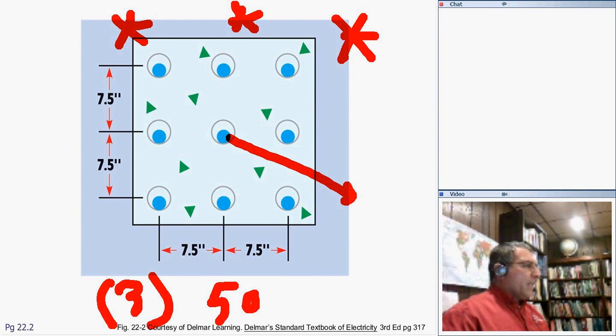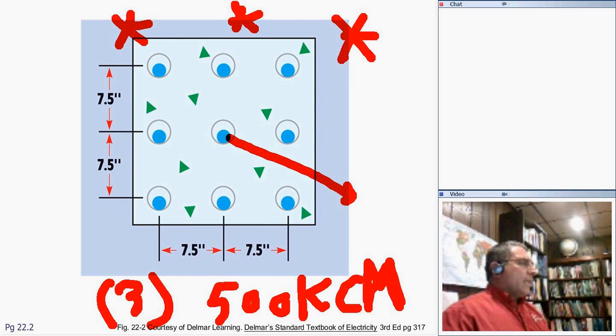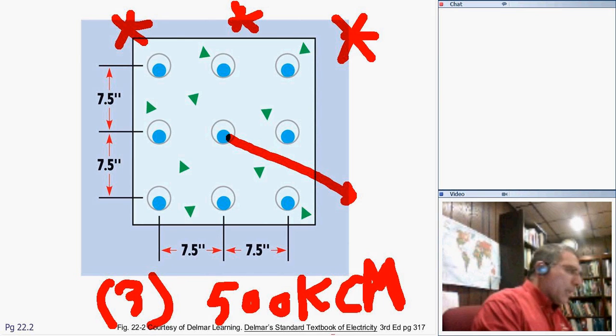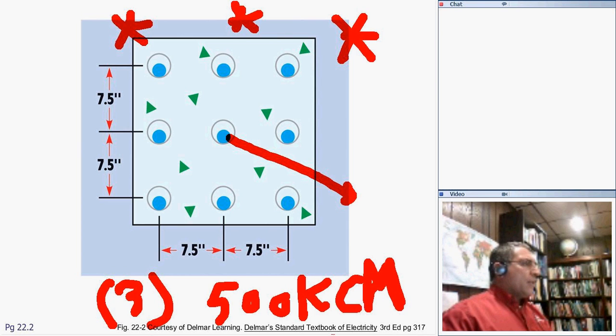And suppose, do you guys remember 500 kcm? Suppose that this here was three conductors in this duct, and each one was 500 kcm. Okay, suppose that's the scenario that we have. I guarantee you that this conductor will not carry 380 amps. If it's three in a duct, in a configuration like that, it would not carry 380 amps. That particular one. So if you put the same conductor in a different configuration, it will.